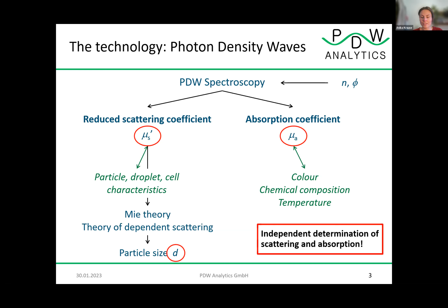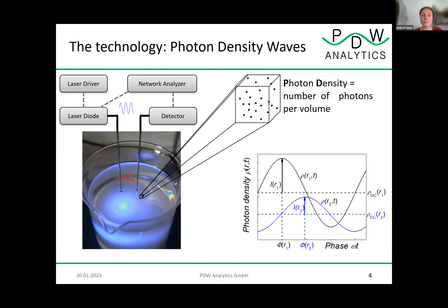This is how the instrument basically works. We have laser light, which is guided through an optical fiber into the material. There it creates, through multiple scattering, the so-called photon density wave, which is detected by a second optical fiber after a specific distance and then analyzed.